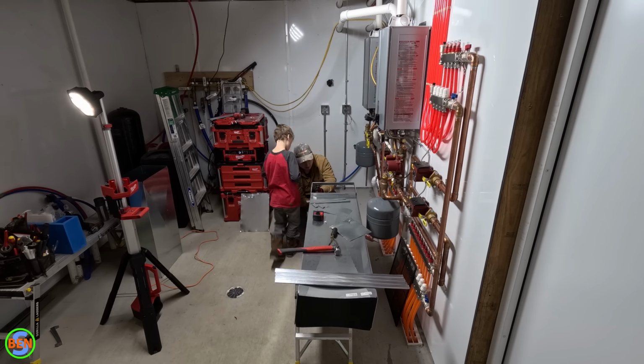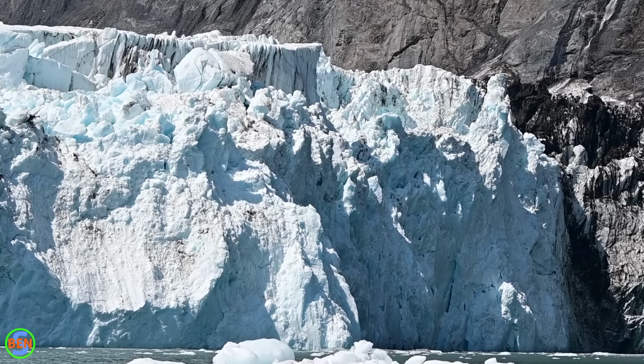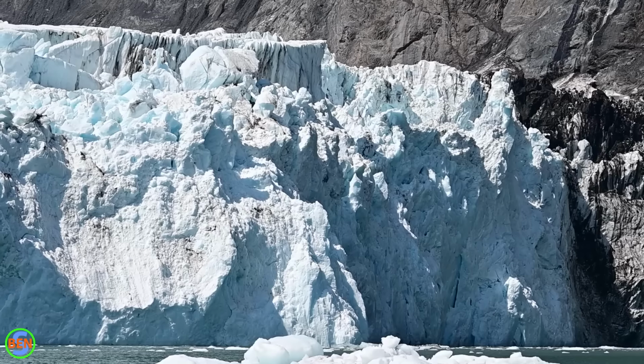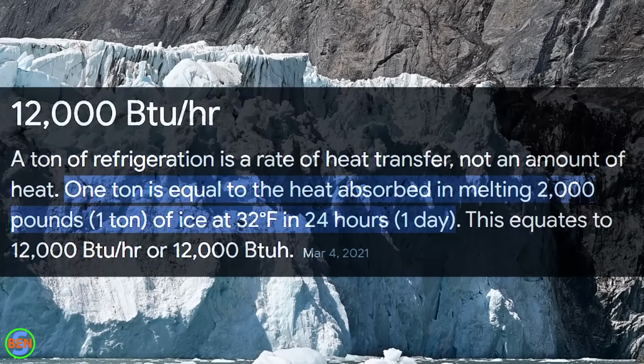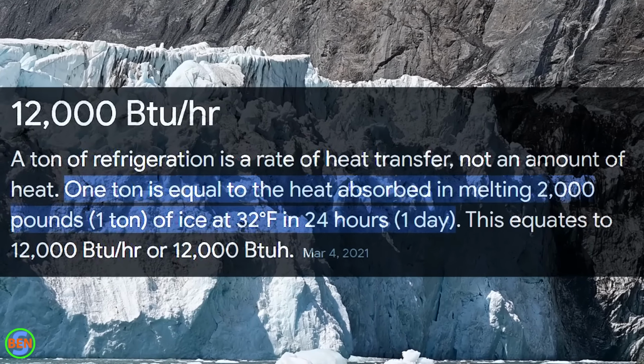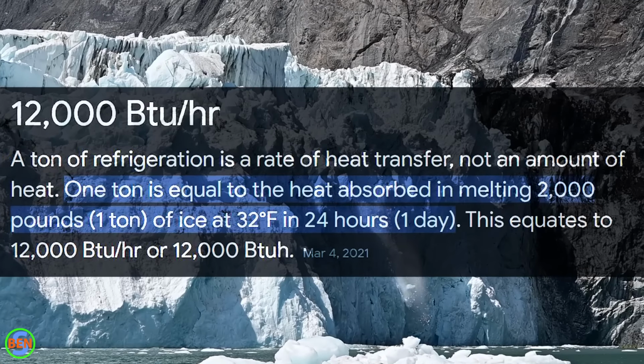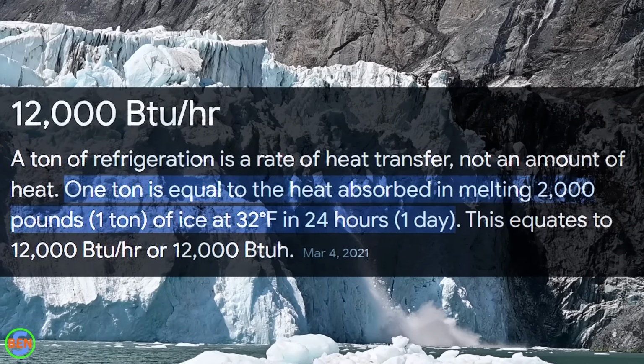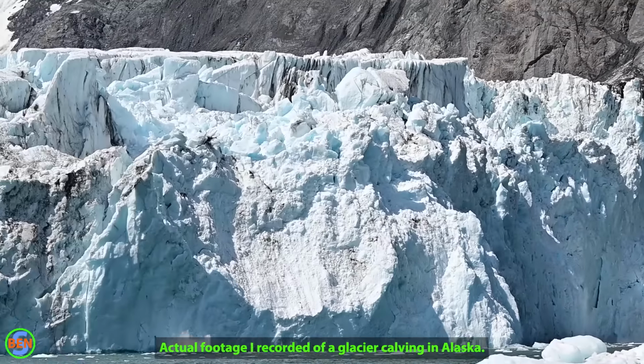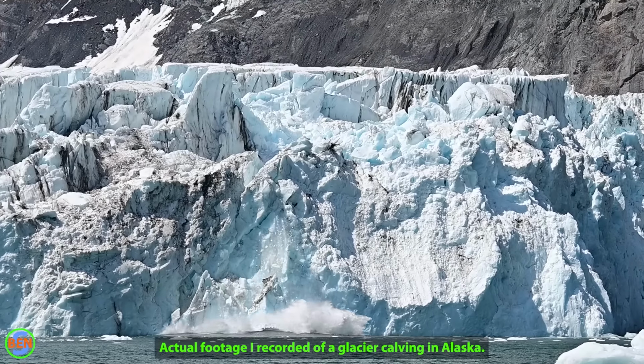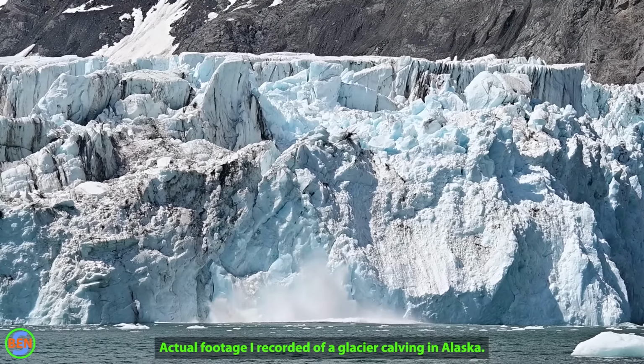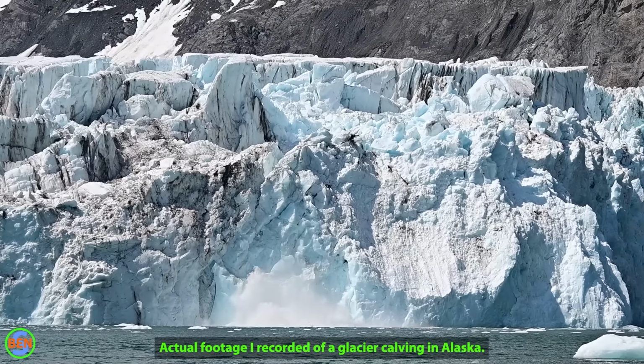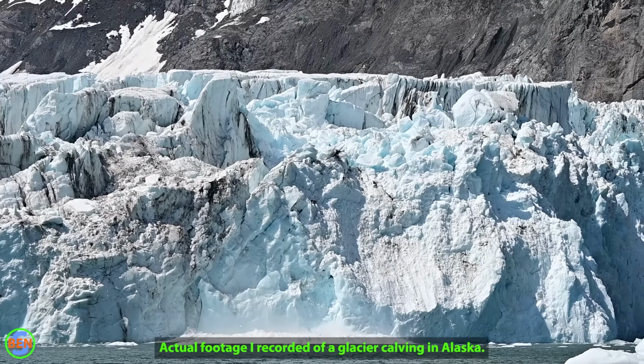And for those of you who are even more curious, I believe that the way they came up with that 1 ton term is that if you were to melt 1 ton of ice, the amount of cooling that it provides is equal to that 12,000 BTU. So really interesting how they come up with all these random numbers, but they do have a reason, just that they didn't translate into the modern world quite like we maybe expected.